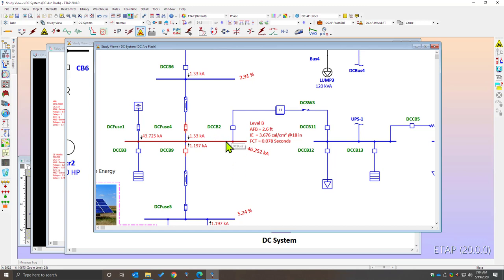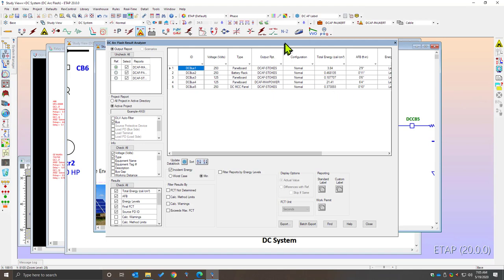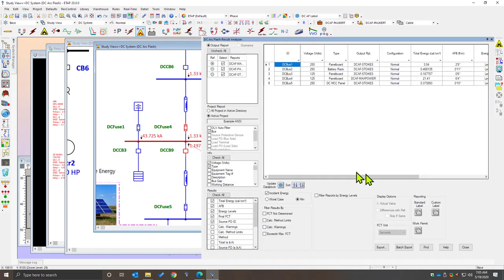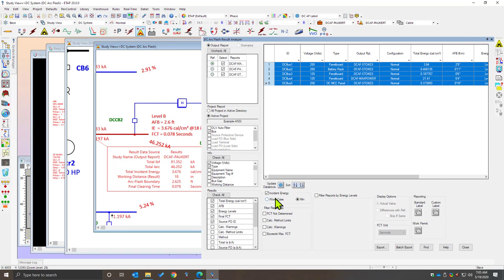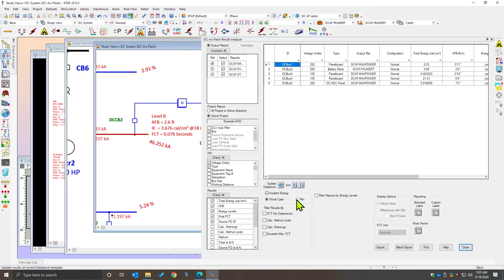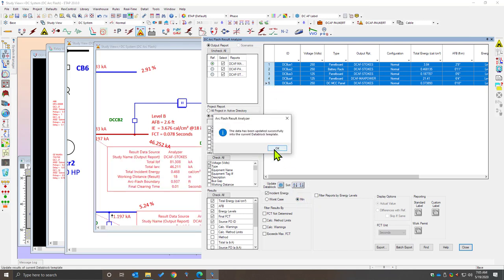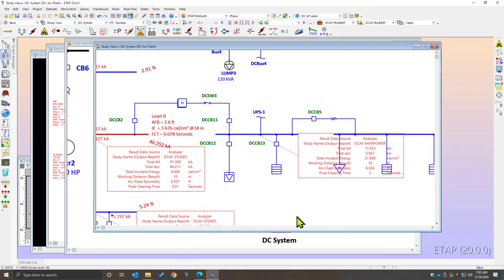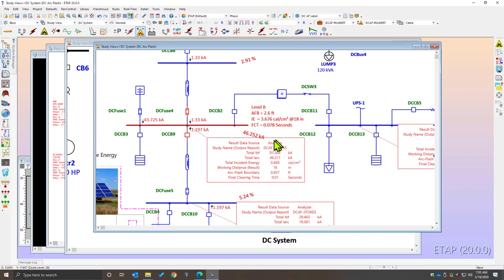First, we turn on our data block to see the data block information, then open our analyzer, which we can dock into our interface. We can select the number of buses in our system, select the worst case incident energy, and simply update the data block. You can also select minimum values and update the data block accordingly, allowing you to quickly update worst case energy directly into the data block for printing and visualization — sourced directly from the DC arc flash analyzer.